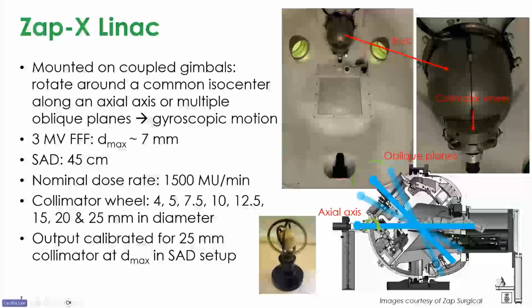And then inside the unit, there is a LINAC. The LINAC is mounted on coupled gimbals and rotates around a common isocenter along the axial axis and multiple oblique planes. So if you think about the principle of a gyroscope, it rotates along the axial axis, and the LINAC can also move in multiple oblique planes and rotate around. The LINAC has only one energy, a 3 MV flattening-filter-free beam, and Dmax is about 7 millimeters, and the source to axis distance is 45 cm. And the nominal dose rate is 1500 monitor units per minute.